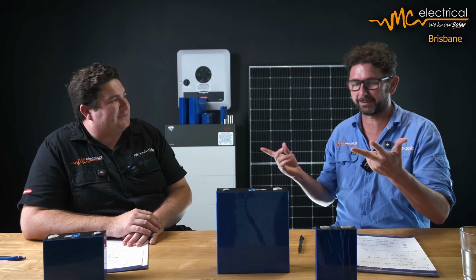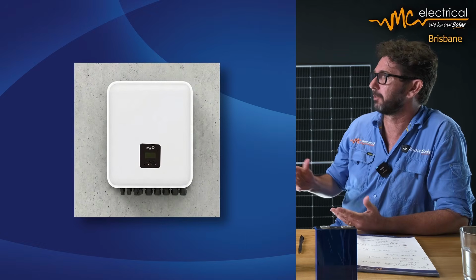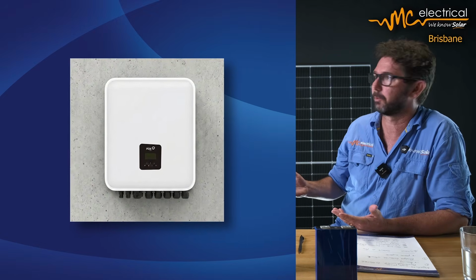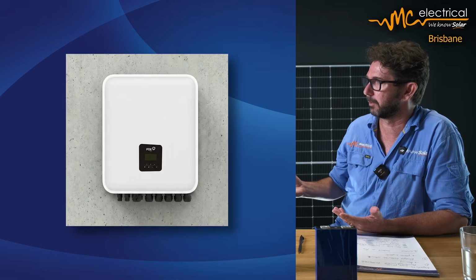Then you can take the phone calls. So that's really limited for a 15 kilowatt inverter. If you're on an 8 kilowatt Fox Smart inverter, three-phase, it's even worse - you've got 10 amps, so basically you can do 3 light circuits. You wouldn't even back up a power point.